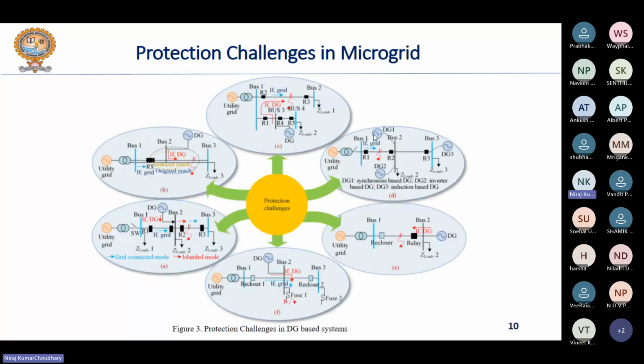So here in this diagram, figure 3, you can see the different possible protection challenges in a distributed generation based system. Suppose here in figure C, you can see one example of false tripping. If you have a fault F present in the system, what should be the desired objective of an efficient protection scheme? It is desired that only the faulty section, that is the line between bus 1 and 2, should be disconnected from the system by the operation of relay R2. If R2 senses this fault and sends a command to the circuit breaker associated with R2 that there is a fault nearby on this particular feeder, it should ideally isolate it.